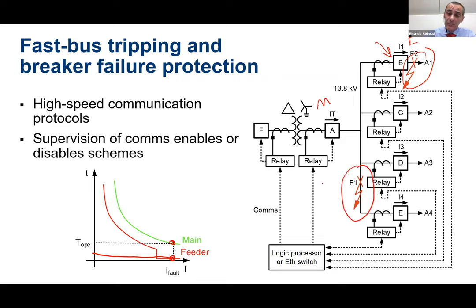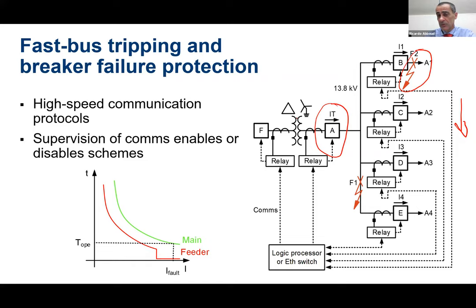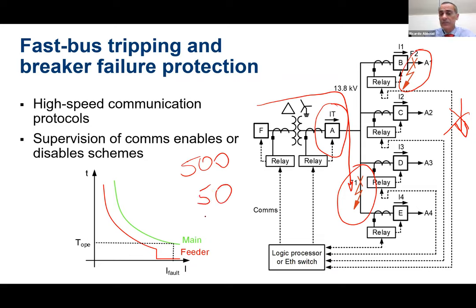When we have a fault in the bus, I'm going to trip in a very long time, sometimes 300 milliseconds, 500 milliseconds, okay? So the idea of the fast bus tripping is to use a high speed communication between the relays. And when I have a fault in the feeder, it will send a block signal to the main relay. In that way, I can implement a fast overcurrent protection function in the main that will be blocked by this block signal. When the fault is in the bus, I don't have that block signal. Why? Because what I have here are the feeders. They are radial. There is no source in the feeder. So the fault current will be flowing only through the main relay, and the main relay will not receive any block. So the main relay, instead of tripping in 500 milliseconds, will trip in 50 milliseconds.